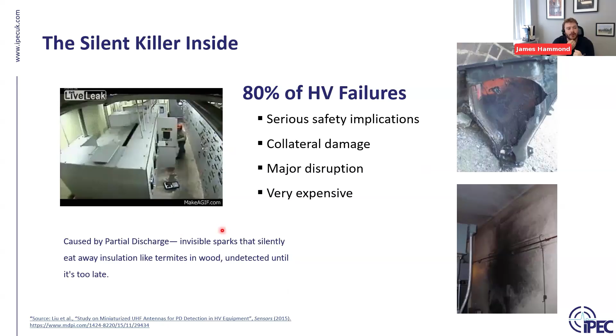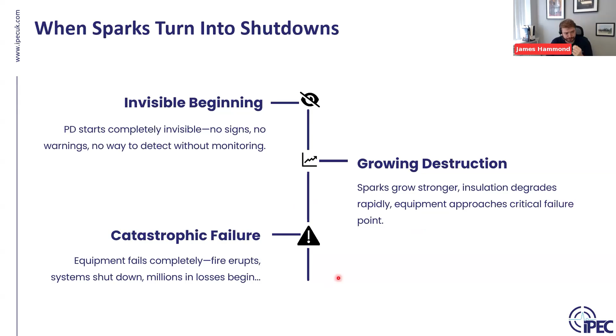Because generally these switchgears are closed. Rightly so, they're kept away and left running. In the UK at least, we've had systems that are getting on 70 years old. So it's something that is growing over a period of time that's invisible. And it grows as well. It gets worse and worse over time, and then eventually you do get that catastrophic failure. And unless there's some type of monitoring equipment and regular maintenance where you can actually get inside the gear, it can be completely unexpected.